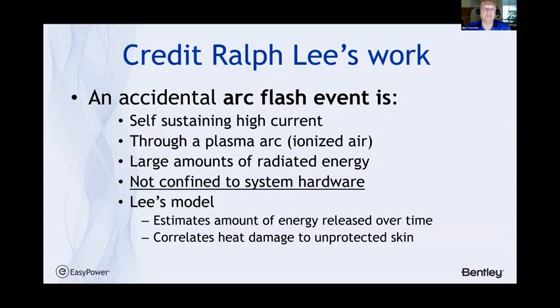And as many times as I've made this presentation or done a workshop, I never had to really define what arc flash is. I took it on as part of this presentation because I think it's not well understood by the layman. An arc flash event is self-sustaining high current passing through a plasma arc, which is ionized air that produces large amounts of radiated energy. The problem, and the real issue, is that this path is not confined to the system hardware, and so its avoidance was not part of the original design. Ralph Lee's model, released in the 1980s, estimates the amount of energy released over time when one of these events occurs and correlates the heat damage to unprotected skin.